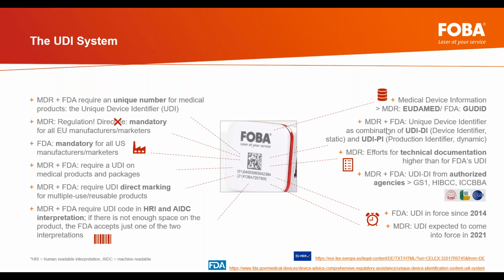So next is MDR and FDA as the UDI combination. And what is the UDI? I want to clarify this up front. So the UDI-DI, the device identifier, is the device itself, so a general description, and the UDI-PI is the product itself. So it describes the product individually. Coming deeper into this later in the presentation. So MDR efforts for technical documentation are higher than for FDA's UDI. So that's why you really need a long period.